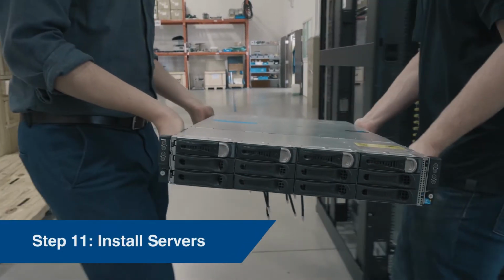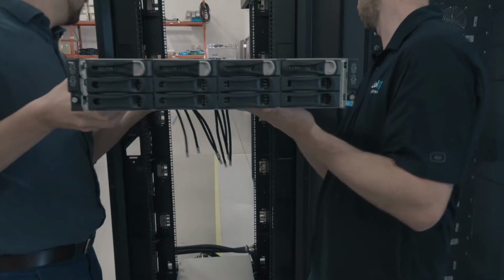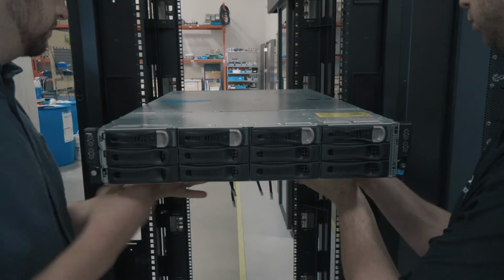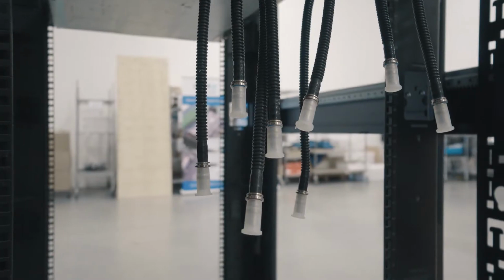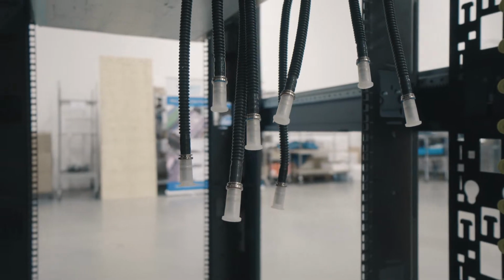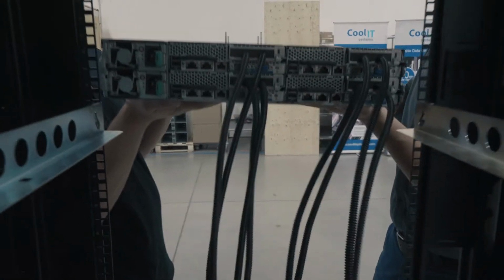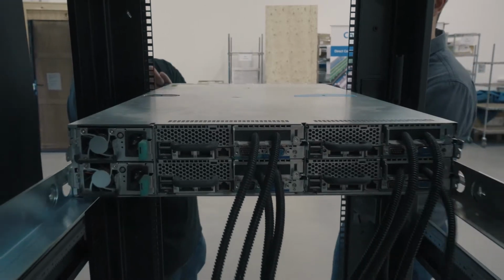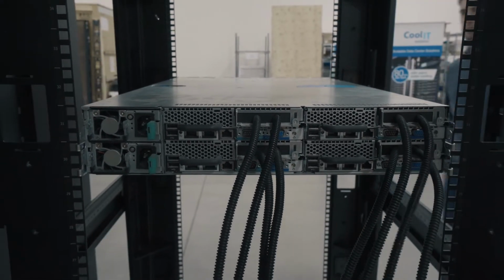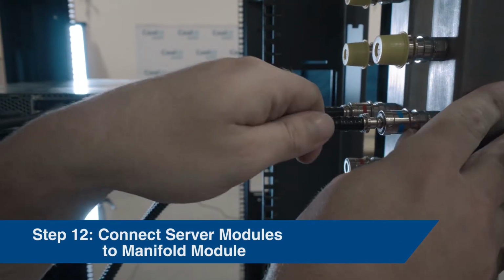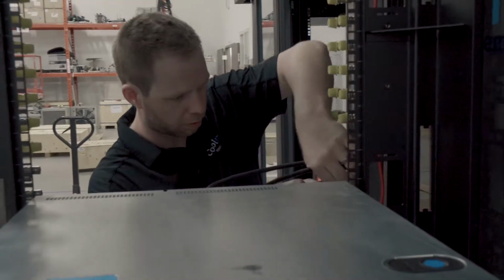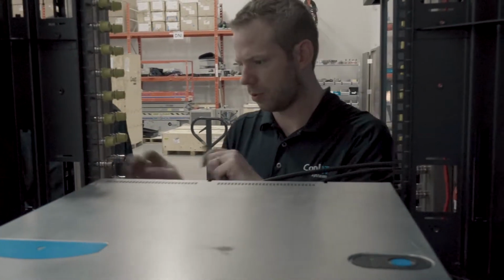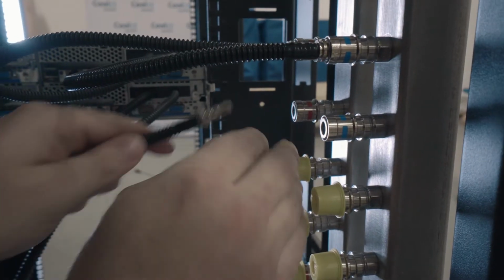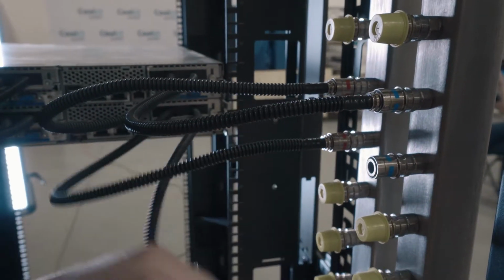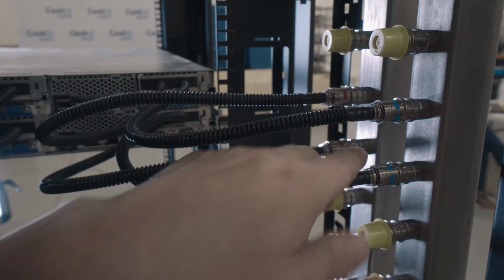Step 11. Installing servers. Install all of your liquid-cooled servers into the rack. Ensure that the server tubing can hang freely after installation and is not caught on other servers. Installing the servers from bottom to top will prevent accidentally catching tubing from currently installed servers. Step 12. Connect server modules to manifold module. Connect the color-coded server module quick disconnect plugs to the mating manifold module quick disconnect sockets. Pull back on the manifold socket collar for it to accept the server module plugs.